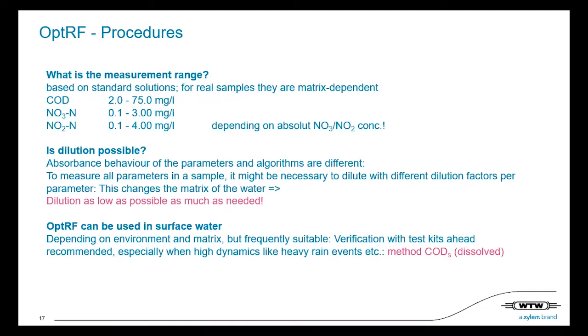Since these are smaller ranges, the question is whether dilution is possible. Since we are measuring real samples and comparing to a real sample in a given range, this absorbance behavior is limited, and we shouldn't dilute it a lot. The rule is: as much dilution as you need, but as low as possible. That's a very important fact with optical reagent-free measurement in the lab with the spectrophotometer.